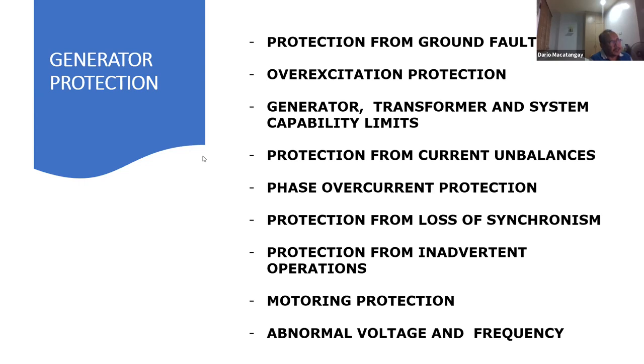Now, as the fault progresses, the inductive impedance of the generator changes from subtransient to transient, so it's a little bit bigger than the subtransient. So the fault current is decaying now, okay? Now, there'll be a time, if the fault is not interrupted, that the current can be smaller than the rated full load current of the generator because of the high synchronous impedance. It's Xd. Xd is many times higher than the one per unit.